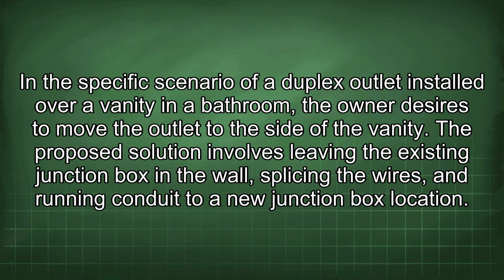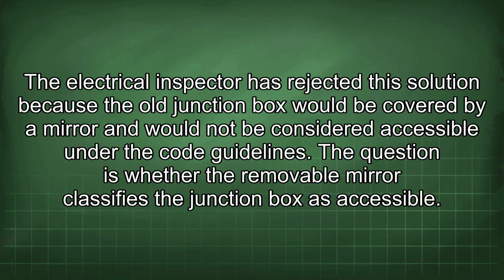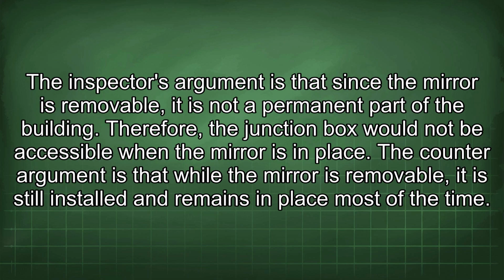The proposed solution involves leaving the existing junction box in the wall, splicing the wires, and running conduit to a new junction box location. The electrical inspector has rejected this solution because the old junction box would be covered by a mirror and would not be considered accessible under the code guidelines. The question is whether the removable mirror classifies the junction box as accessible. The inspector's argument is that since the mirror is removable, it is not a permanent part of the building. Therefore, the junction box would not be accessible when the mirror is in place.